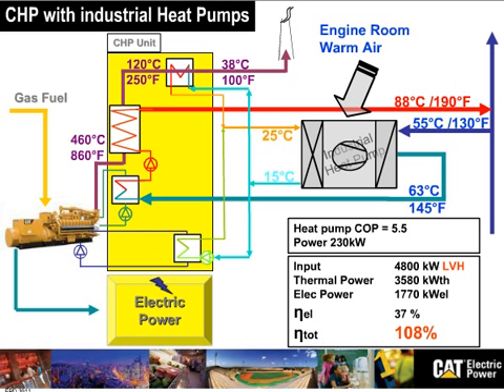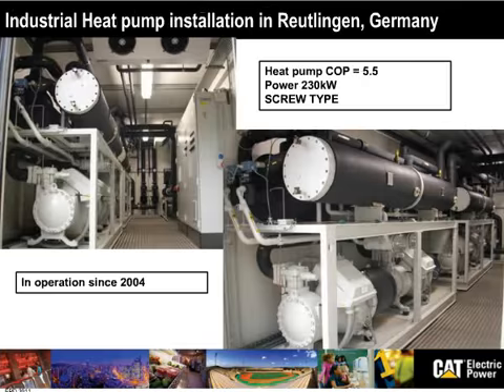The next slide is exactly the heat pump. This is a screw-type heat pump that has been used in Germany since 2004. It's COP 5.5, screw-type, very efficient, very robust. We've been running for now more than 7 years, and it's a very good success for the customer, a lot of heat. More heat, more usage. What can you do with heat?